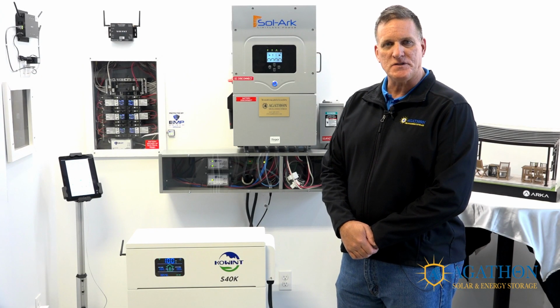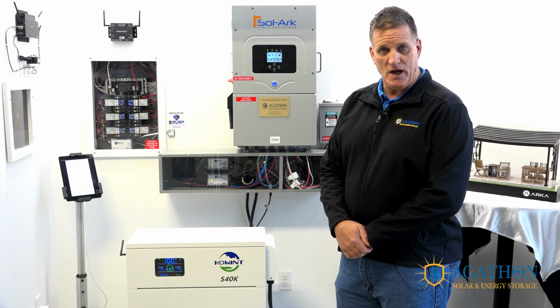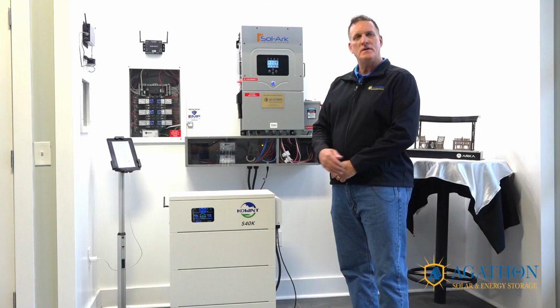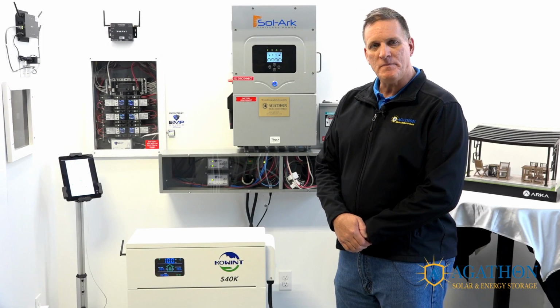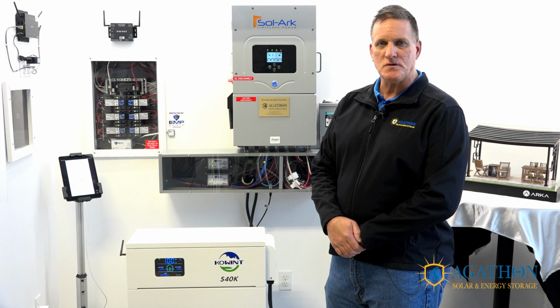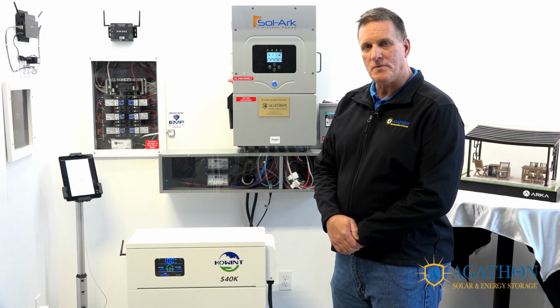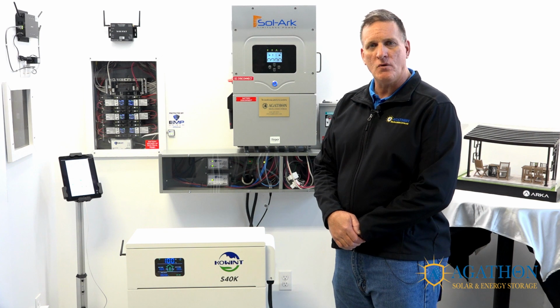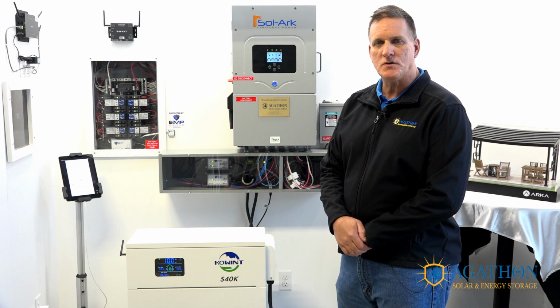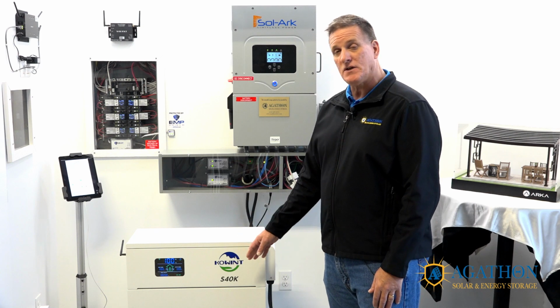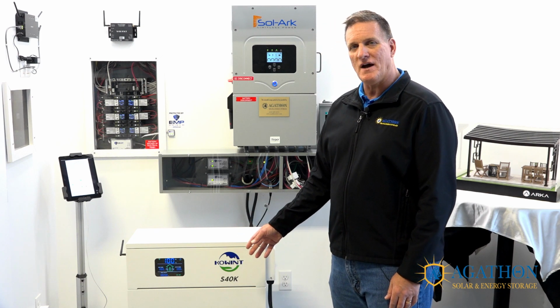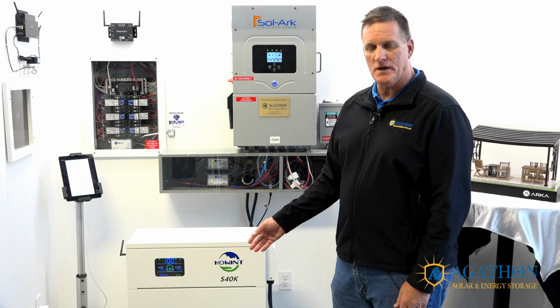Having come to a fair understanding of how much energy you'll use at night or when there's no sun, you can now size your battery system. Keep in mind that although some manufacturers say batteries have 100% depth of discharge, we recommend always leaving at least 20% in your battery. So if you have 10 kilowatt hours of energy storage, you really only have 8 kilowatt hours of usable storage. The Kowint S40K has a 10-year warranty and 6,000 cycles at an 80% depth of discharge.